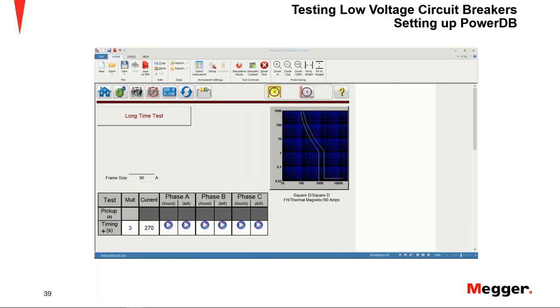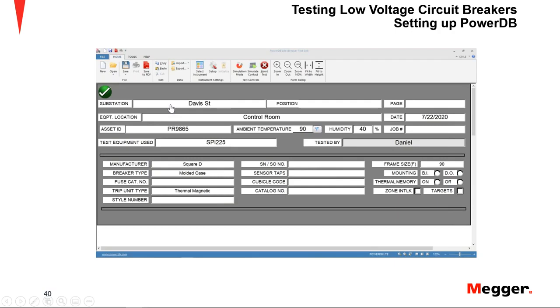Before we dive into the testing itself, I want to show you another section of the software, which is the nameplate. If you click this button right here, the blue icon in the top, you will get presented with the screen. So you can fill out identification information. Important, so your report looks better and you have all the identifications both for the breaker under test as well as the conditions: the location, even temperature, humidity, the name of the person running the test, if you have a job number, and so on and so forth. Like these will be part of your report. So it will take you a couple of minutes to fill out. And then we can go into the measurements themselves.